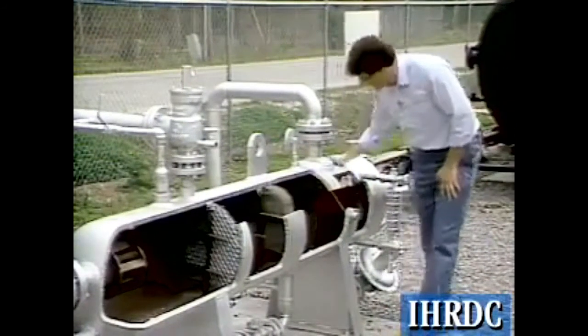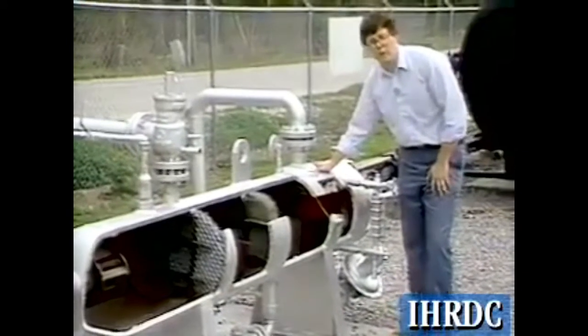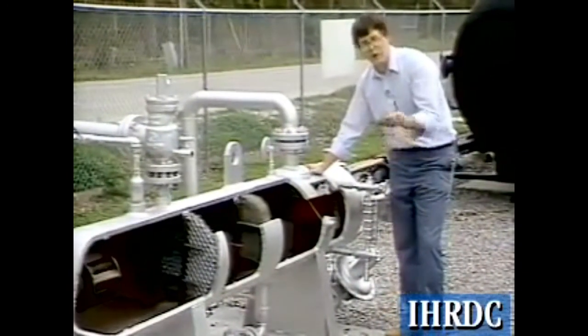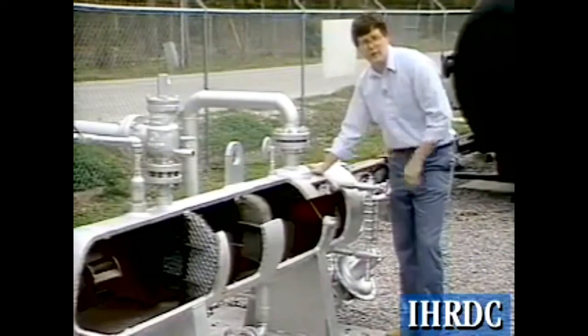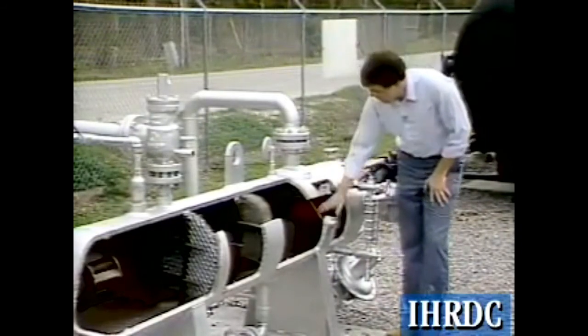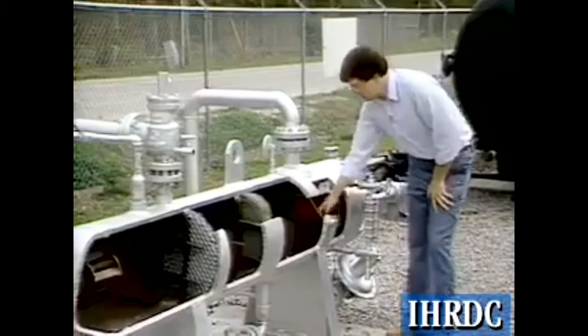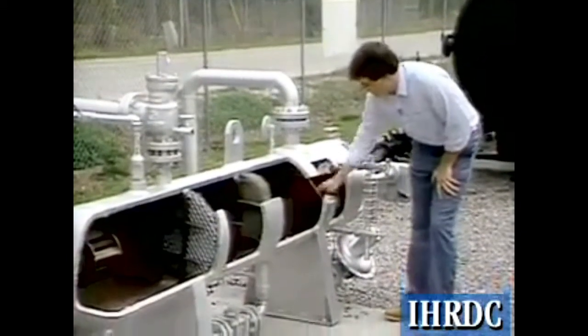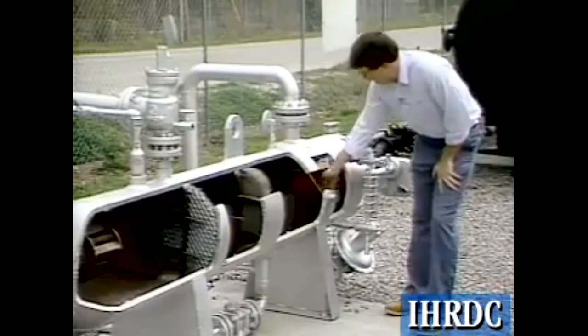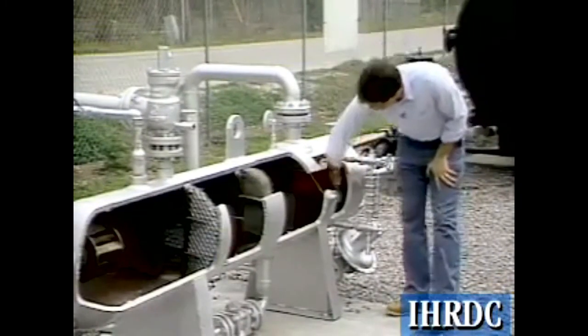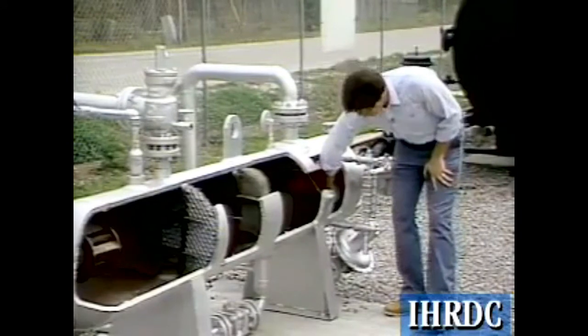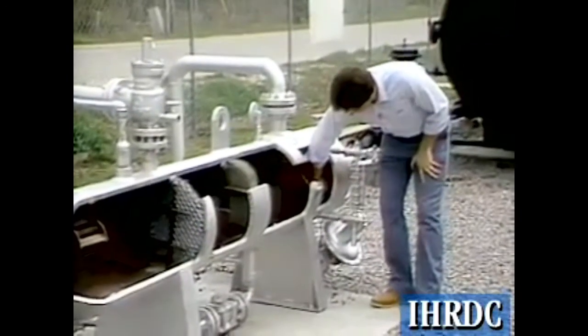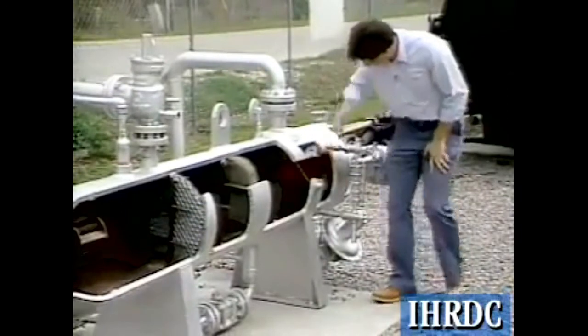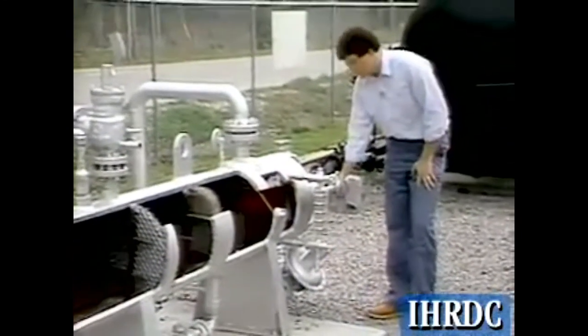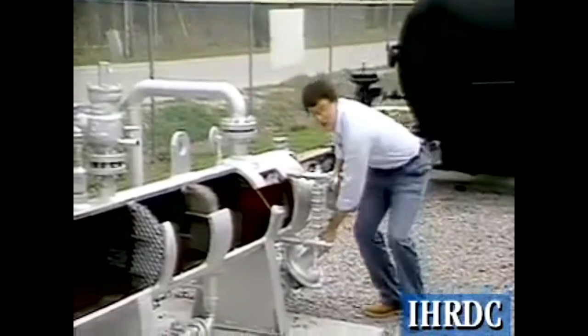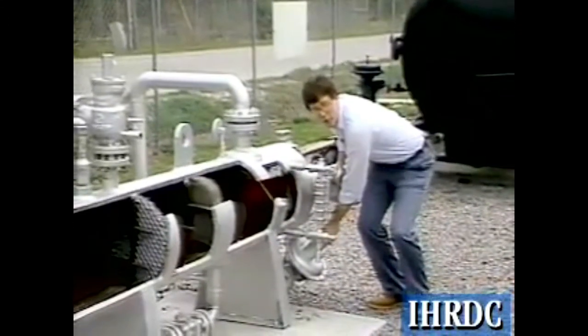And finally, we get to the end of the separator that's responsible for the separate dumping of the oil and water phases after they've been separated. We see here this weir which allows the oil on the top of the water to spill over into this bucket here, which is monitored by a float or a level displacer inside this bucket, which operates this controller, which operates this liquid dump valve down here for the oil phase.